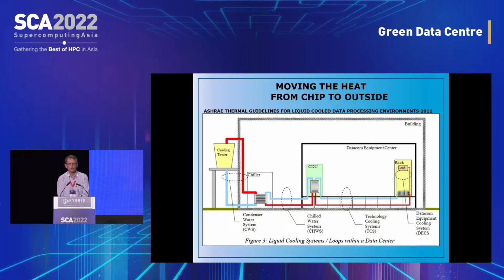In this diagram they've still got a chiller. But think about it: if you're looking at a 65 degree chip temperature, and you could use 40 degree liquid to take that heat away, do we really need the chiller? We shouldn't, because at that kind of temperature we should be able to go directly to the cooling tower. We also don't necessarily need so many steps of heat exchange. We can reduce the number of steps.